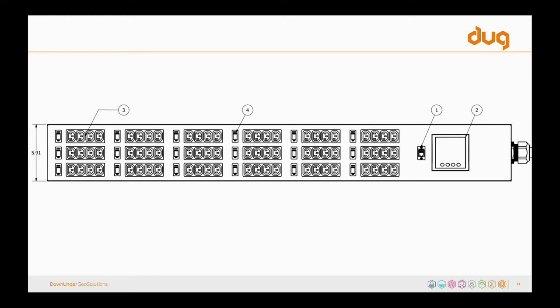Then downstream from the PDU, of course, we have the power supplies themselves. If you look at the gold, platinum, titanium power supply ratings, you'll find that in every case, for every workload, it's somewhere between 2 and 4% more efficient to run them at 240 volts than 110 volts. Most of the time, things like this aren't captured in PUE. People tend not to capture losses due to transformers and power supply overheads, but they're very real and we pay for them all the same. So we try to look at every aspect, the whole power supply picture, if you will.